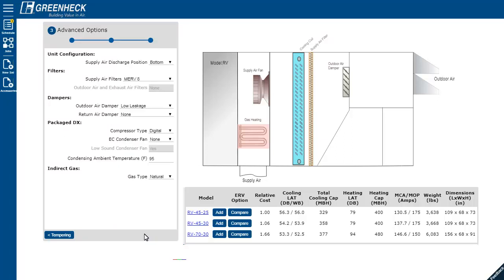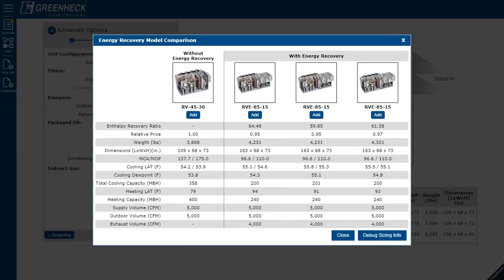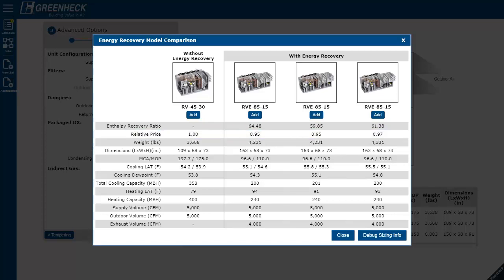You can also compare this standard unit to a unit with energy recovery. In some cases, like this one, you might be surprised to find the unit with energy recovery is less money. It's because the required mechanical cooling is so much lower.